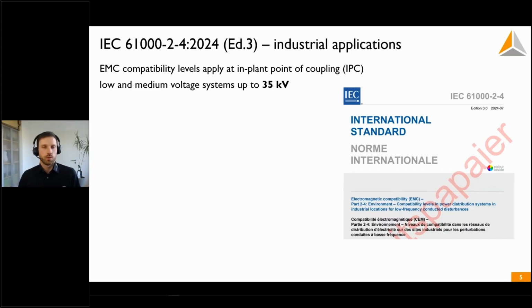This covers all voltages up to 35 kilovolts. But what's new in this standard? Well, something that is new is the previously highest order for the THD, the total harmonic distortion, was up to the 50th order. Now it's up to the 40th order. So they kind of adapted to the other standards worldwide, which also go up to the 40th order for the total harmonic distortion.